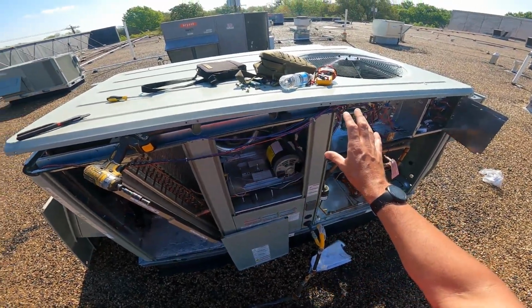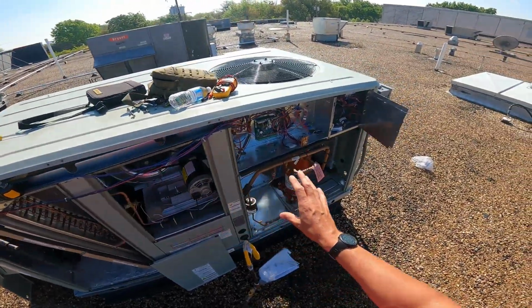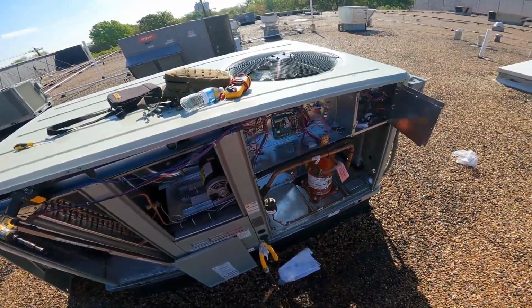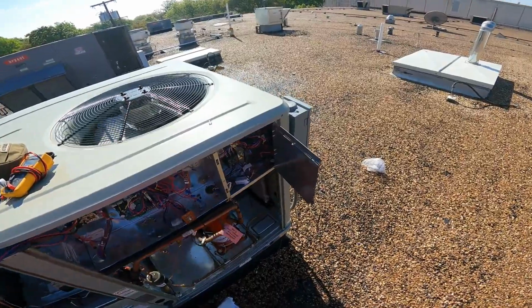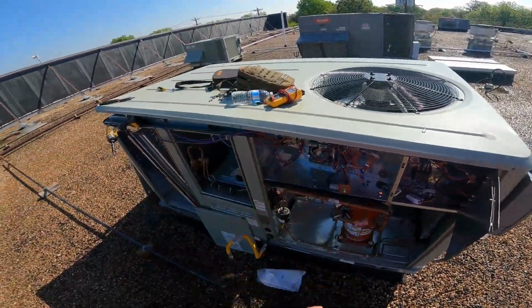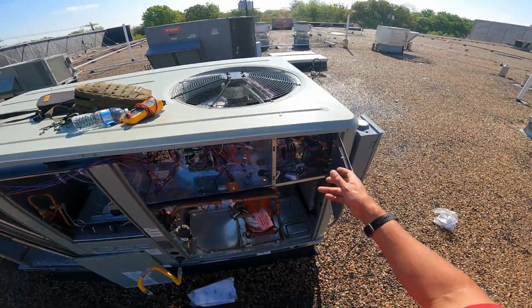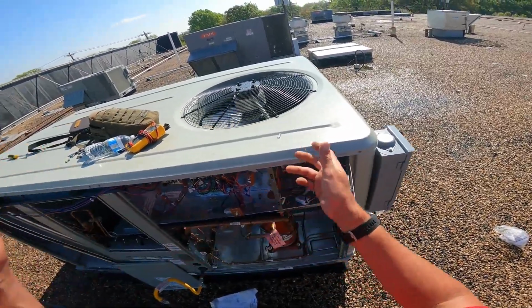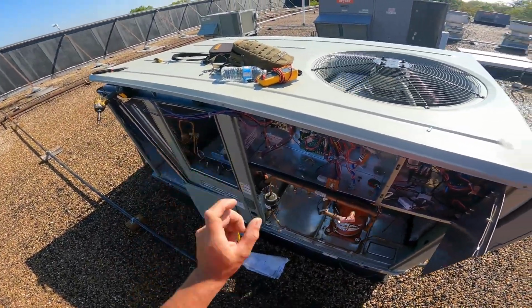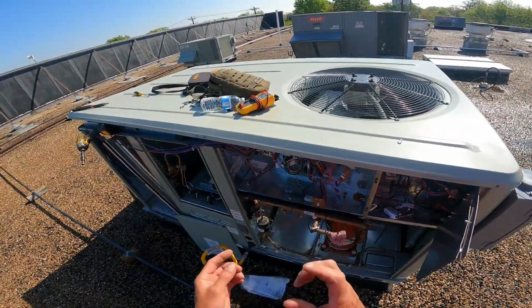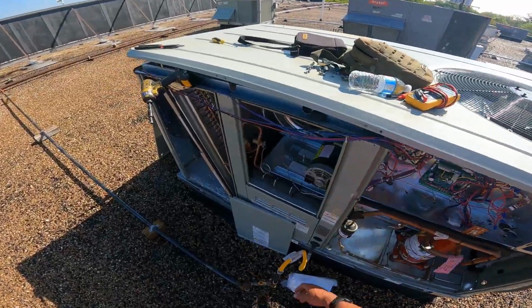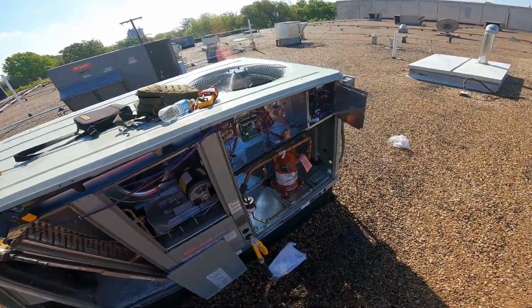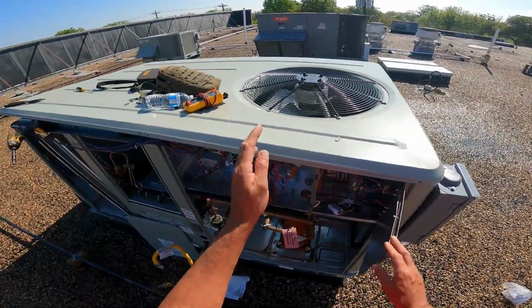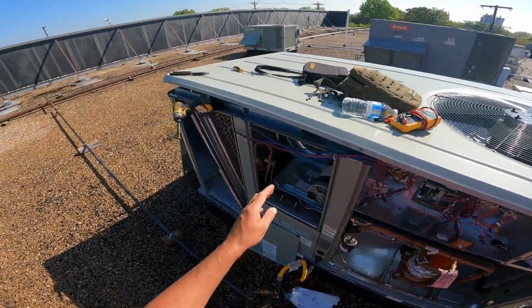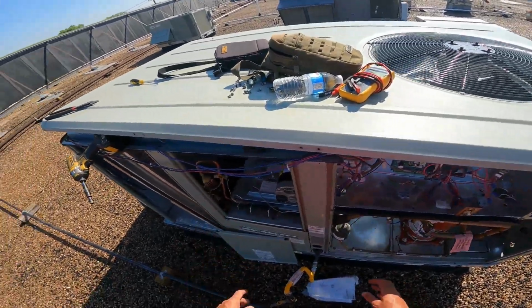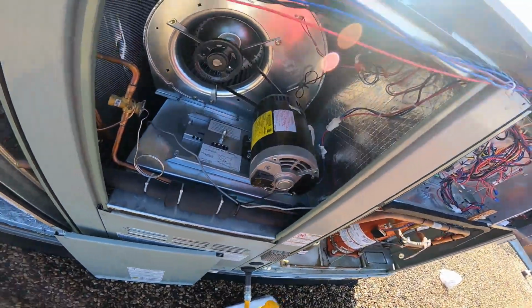Anywho, that's all I got for you today, because low voltage, the whole idea behind this was tracing out low voltage. And the takeaway is, it sucks, okay? Sometimes it's simple and you just gotta check your contactor coil that's just not doing right, in which case you can pull the contactor, smell it, use the sniffer, and it'll tell you if that thing's burned up. Otherwise, when it comes to something like this, you just have to pick it apart one at a time. Start tracing from your transformer one wire at a time until you figure out exactly where that ends. And today, that ends at that fella right there, my mixed air sensor.